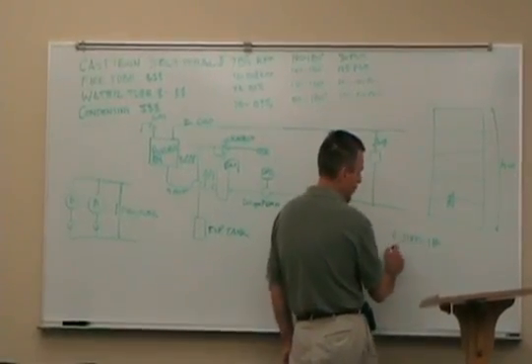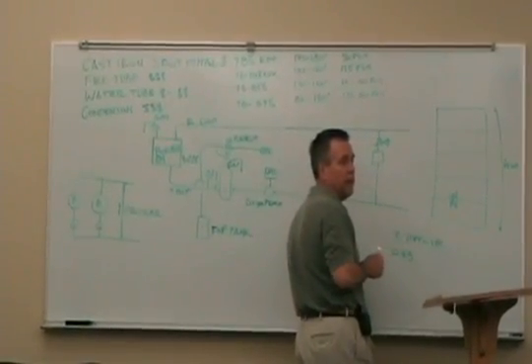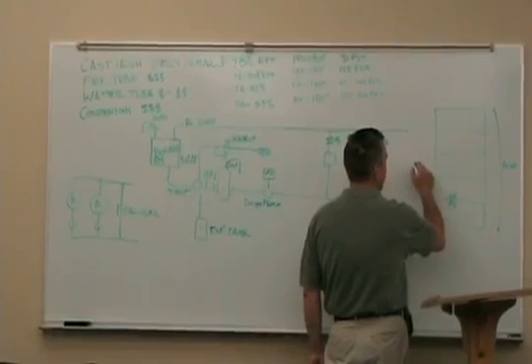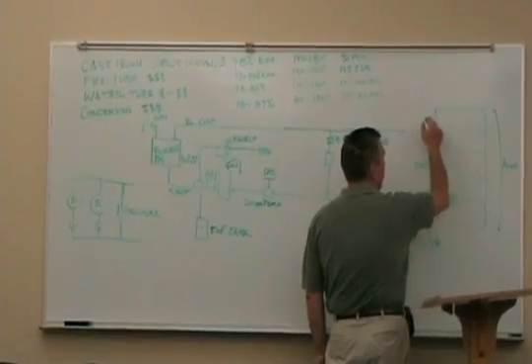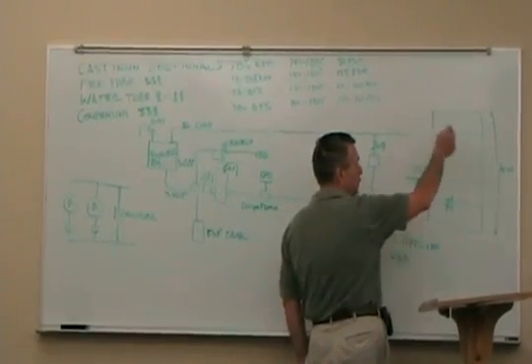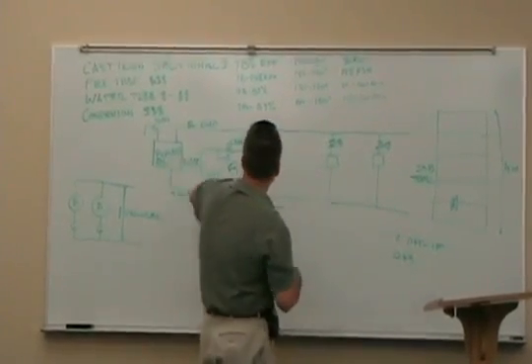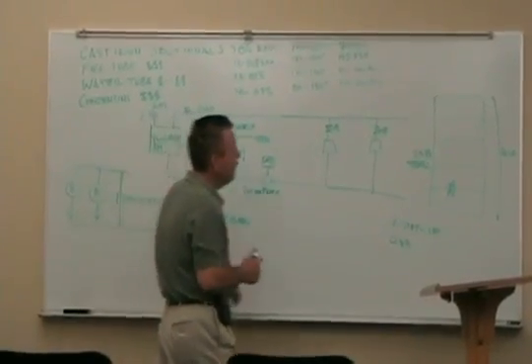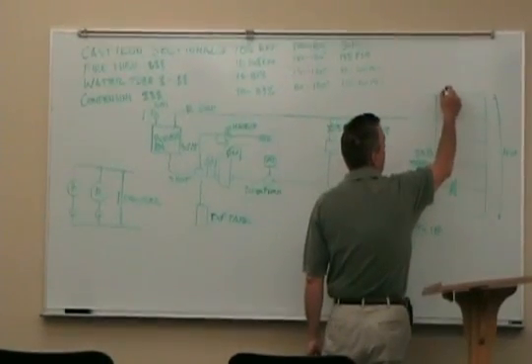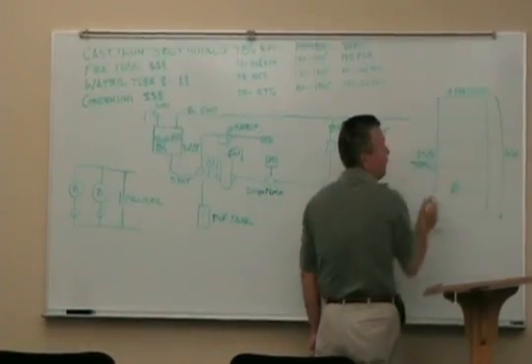Okay. Reciprocal, that is 0.43. A little easier, just multiply 60 times 0.43. Okay, that's kind of the number we picked out the other day. 25.8 is my static head. Now, I also want to make sure that I've got at least some positive pressure up here in case, like in a boiler application, you may have something go haywire, and up here we've got 212 degree water. So you want to make sure that you've got positive pressure up here in your piping loop so that you don't flash the steam.